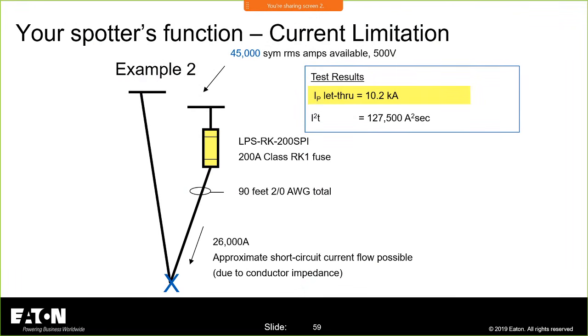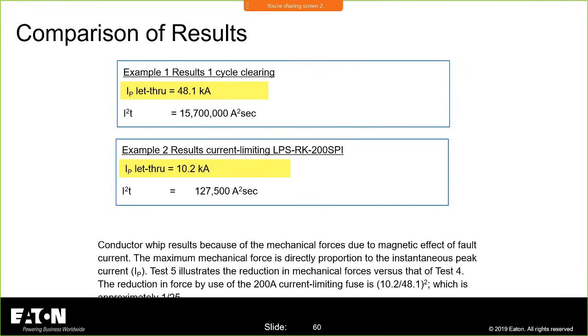And what we've done by the use of the current limiting nature of the fuse, we reduced that peak current for that half cycle, which was 48,000 amps. We reduced it down to 10,000 amps. That's why we didn't see as much magnetic forces on that conductor. And we took the heat from 15.7 million amp squared seconds to 127,000. That's a huge reduction in the heat and the magnetic forces.